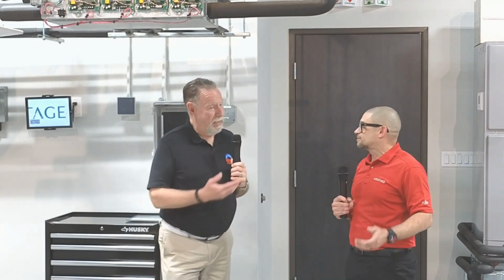So you have some flexibility there. You're not going to put 150% of indoor unit capacity and magically get that much—you still have the same capacity as your outdoor unit. But throughout the day, the load moves around depending on where the sun is and who's in the room. You won't be in every room every time; some units will be off. So it's like having control of each space in your house without dampers or zone boards, just a controller in each room to manage the space, and you save energy.